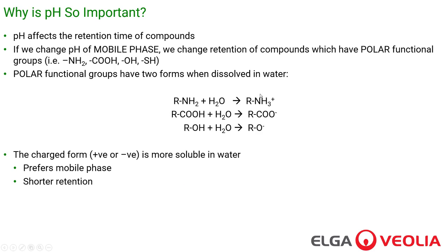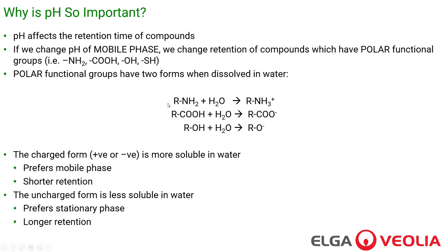The charged forms are much more soluble in water. They will prefer the mobile phase, have less affinity for the stationary phase, and will have shorter retention times. So if we don't control pH, the substance has a very unstable retention time. The uncharged form is less soluble in water — it will prefer the stationary phase and give us longer retention. Mobile phase pH controls this equilibrium. We can shift it one way or the other to make the substance charged or uncharged by modifying the pH of the mobile phase.